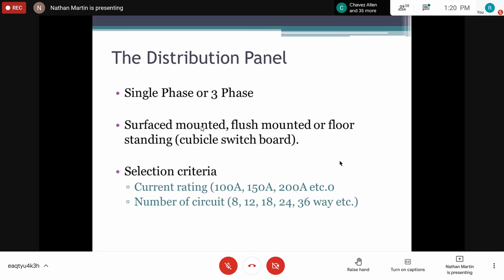All right. Surface mounted, flush mounted, or floor standing cubicle switchboard. So what we are saying is that your panel or distribution panel can be surface mounted. It can be flush mounted. That's when we have to chop the wall or cut out the drywall and install the panel. Or it can be floor standing. Now, the floor standing is what you'll find in large facilities, such as UTECH and some other facilities. You'll have a standing cubicle, right?